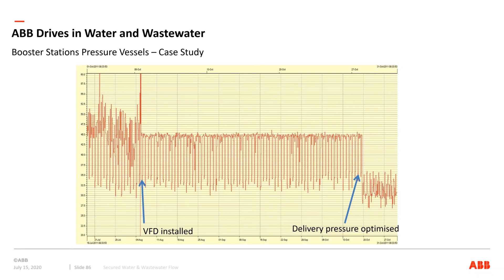And then this is also taken to maintaining a constant pressure, using a pressure transmitter in the loop, not just a pressure switch. If we use a pressure switch that turns on at 50 PSI and turns off at 90, by using exact pressure control for PSI control, we can maintain constant pressure plus or minus 1, 2, or 3 PSI.